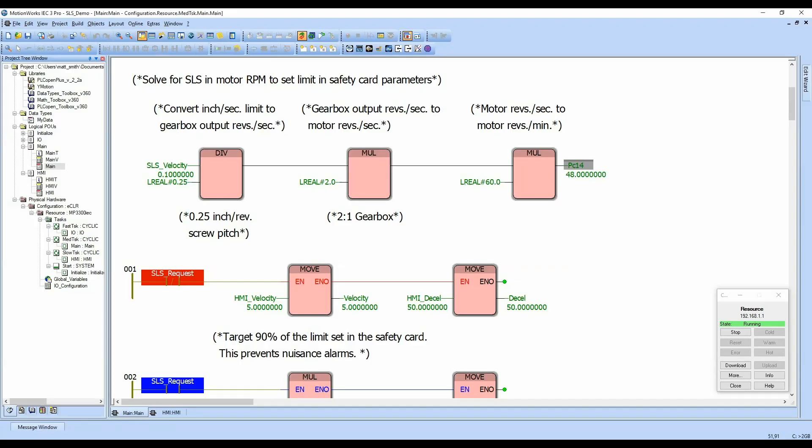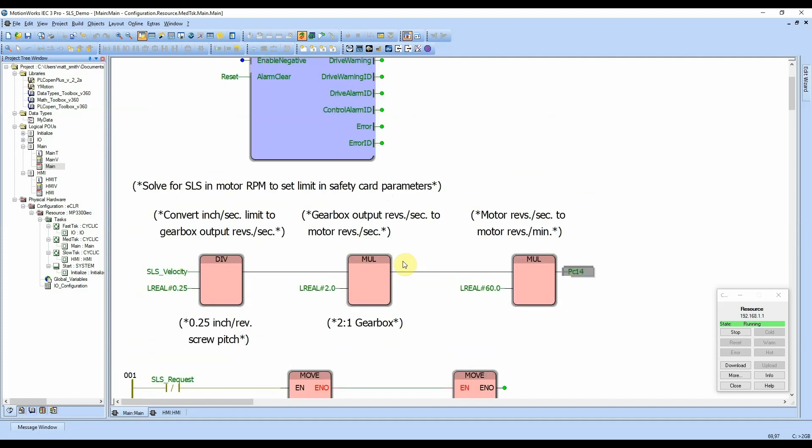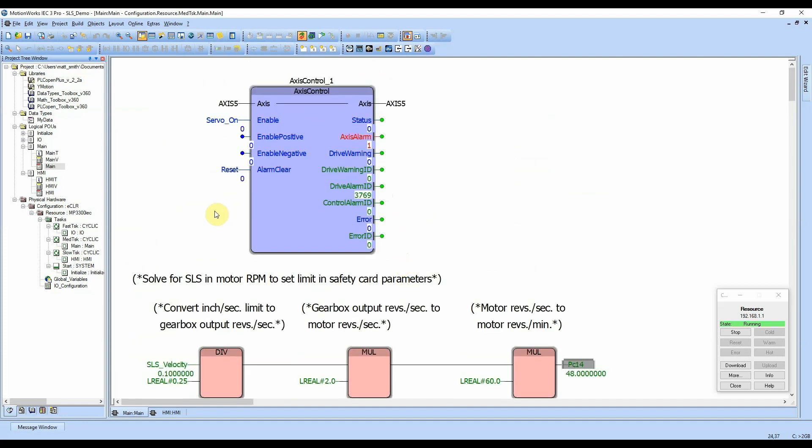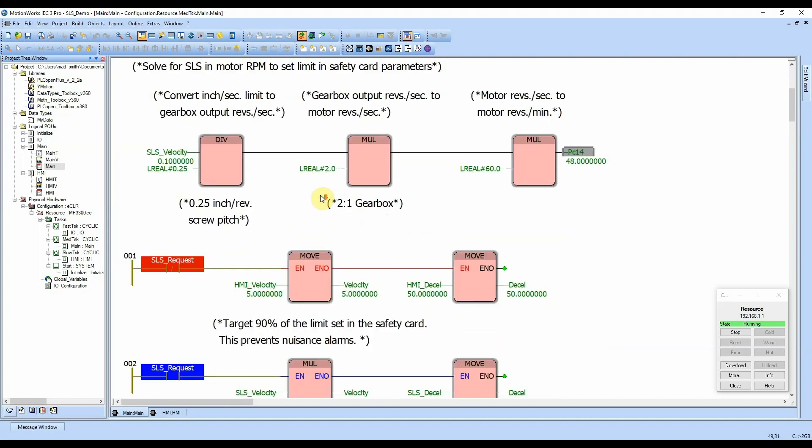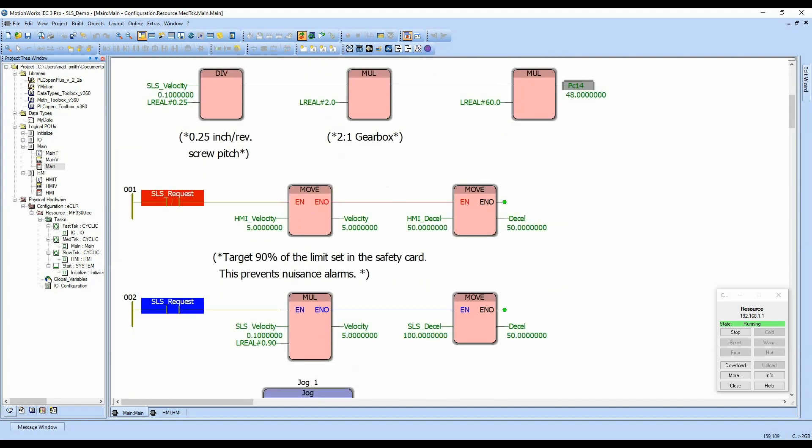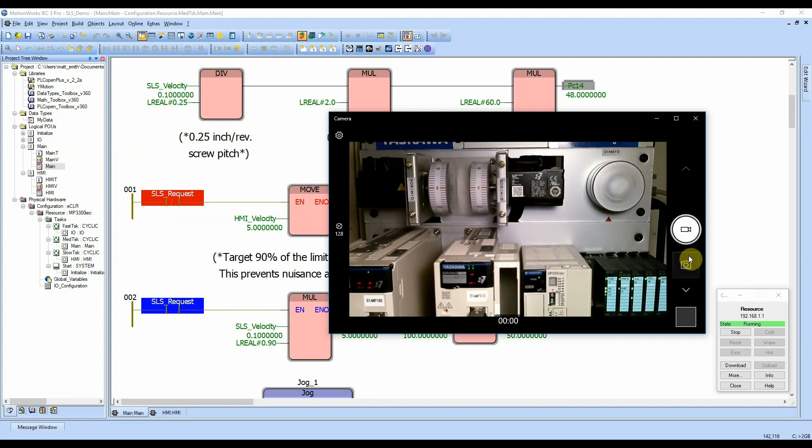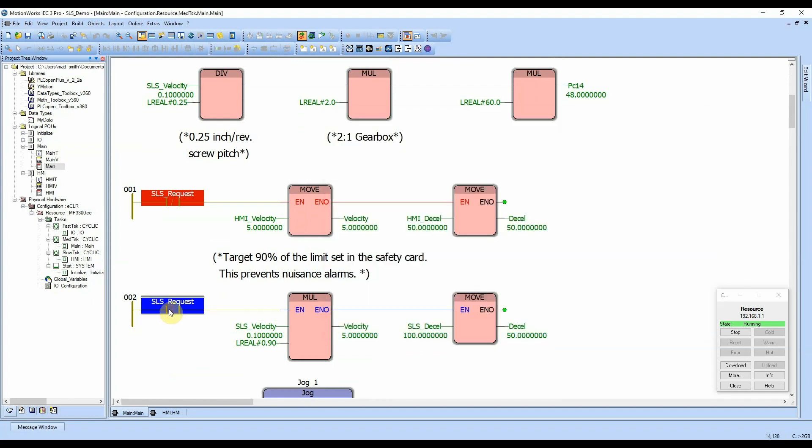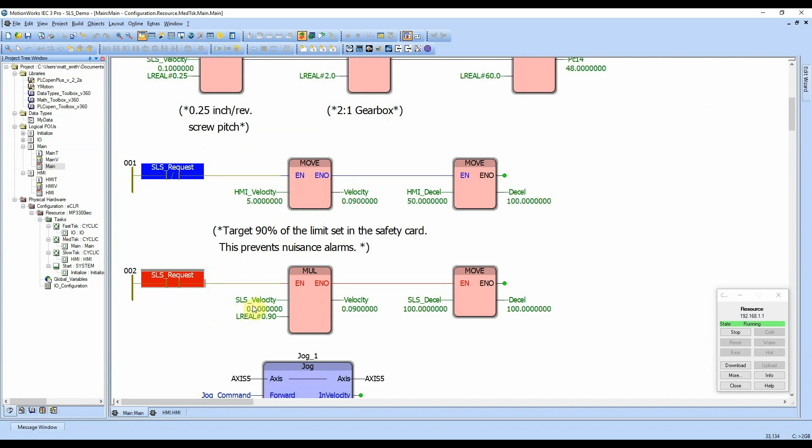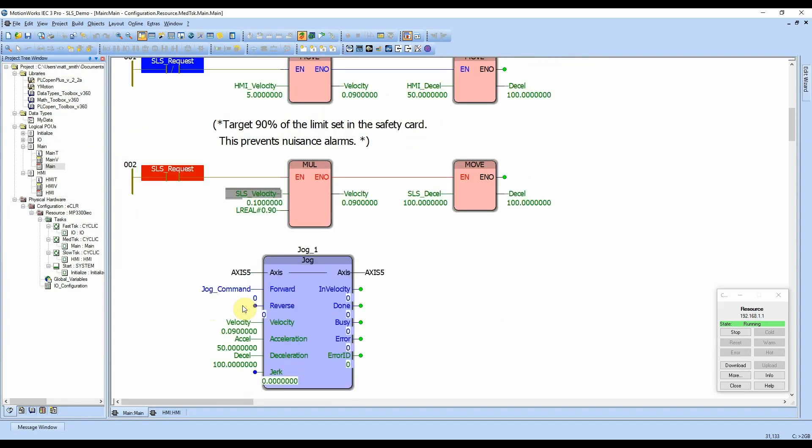What we can do now is look at our MotionWorks program. And then up here at the top, we'll have an alarm on the axis. So we can reset that. And we can enable the servo. And then set up a webcam here. So in normal operation, we've got a fast jog speed here. So definitely not safe. And then we've got an input into our program. It's coming from our safety PLC. And when that drops out, it's telling the controller that you need to keep that velocity or speed of the motor below a certain level. Just to give a little fudge factor, we actually command about 90% of what we've parameterized the drive for just so there's no false errors.